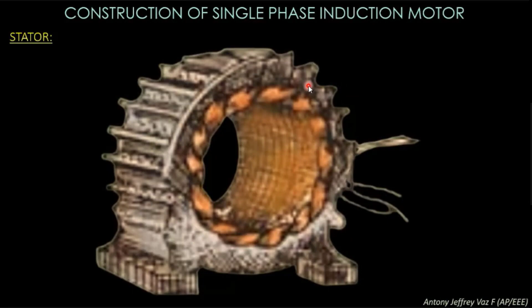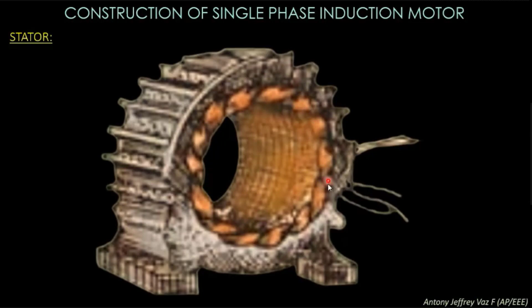Next, here is the stator. This is the stator of the induction motor. You can see this outer part is the frame. Inside you will have the stator windings. If you have a three-phase stator winding, then it is known as a three-phase induction motor. If you have a single-phase stator winding, then it is known as a single-phase induction motor. So in the stator windings, you have two different options. If you wind the stator for single phase, it is a single phase induction motor. If you wind the stator for three phase, it is a three phase induction motor.